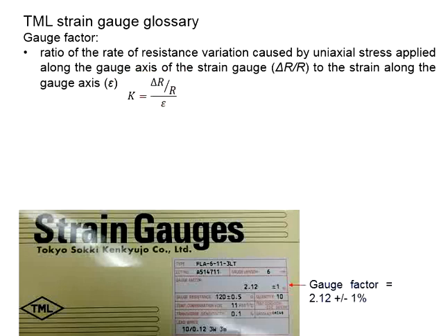As far as the data logger is concerned, the data logger is actually measuring the change of resistance. The computation will be finding the ratio between the change of resistance against the original resistance. Now, if we key the gauge factor into the data logger, it will help to compute the strain, and as a result, the strain is displayed.